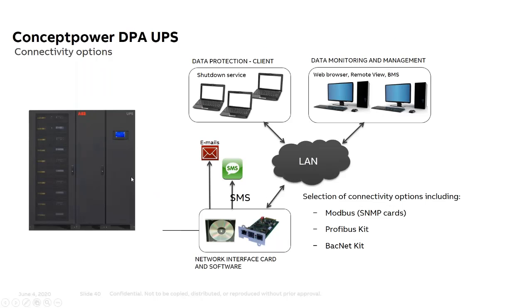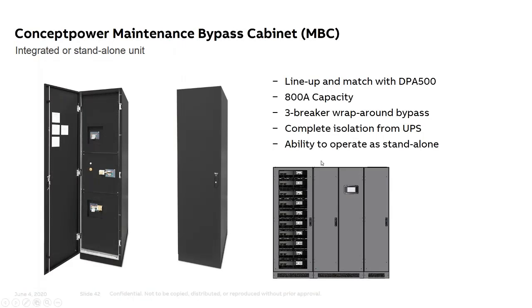But what we see a lot more is online monitoring. Modbus is in the data center market the most popular, but some use SNMP. The cooling guys, the mechanical guys, seem to like BACnet a lot. Profibus is primarily used in Europe, but it's a protocol that's mainly used in industrial applications. The short version of this is we support all of them with the ABB UPSs.